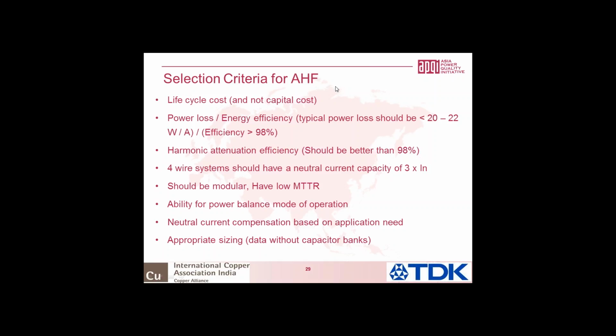This brings to the last slide of the session, where I've listed down some of the solutions. You have simple shunt capacitor banks, detuned capacitor banks, partially tuned capacitor banks, tuned passive filters, hybrid harmonic filters, and active filters. And every column tells you what they can do. Fundamental VAR compensation, yes, all of them can do, and all of them can improve the displacement power factor. The next column is harmonic amplification and reduction in DPF. Yes, if you have a simple capacitor bank, it's possible. You will get a lower distortion power factor, whereas all the other cases, they are perfectly fine.